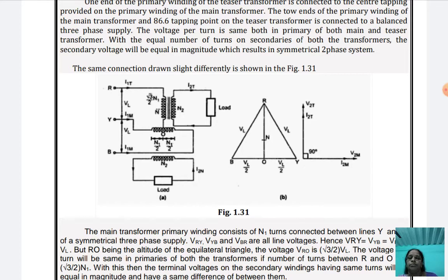But the main winding N1/2, that is the primary, is divided into two equal windings only. So the primary current I1 of the main transformer is divided equally by 2. In the vector diagram, the teaser transformer and the main transformer are, as I already told, 90 degrees out of phase.